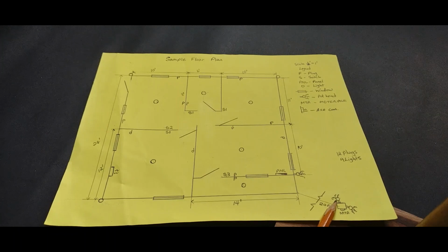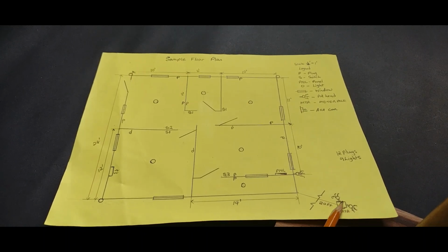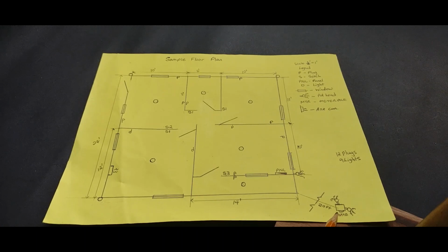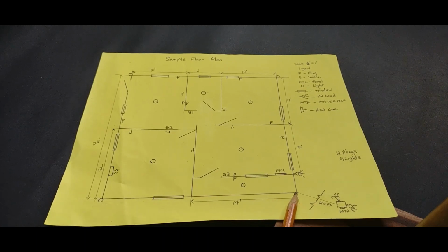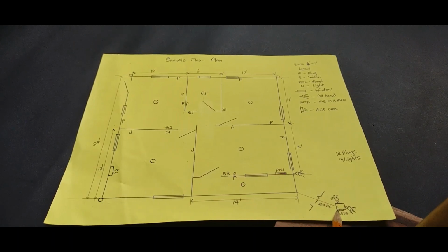And as you can see, when you see two potheads, you know that it will be an overhead wiring. If you see one pothead, it would mean that the wire comes in and then goes through the meter and then goes underground into the building. But in this case, it will be an overhead wiring.